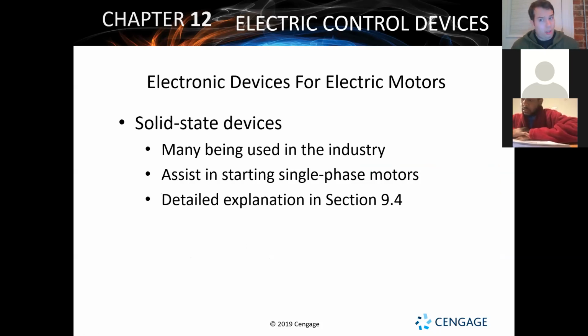So again, third time tonight, solid state devices. We're talking about control boards. We've got a lot of different ones we're going to see used. They are used in a lot of different ways for single phase and for 3-phase motors. So remember, with a single phase motor, you've got power coming in. It goes to your run and your start windings. And then ties back to common.